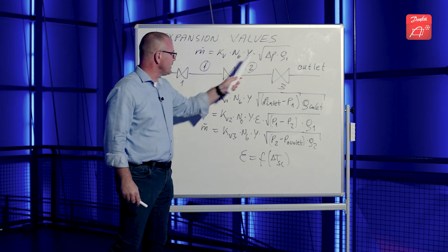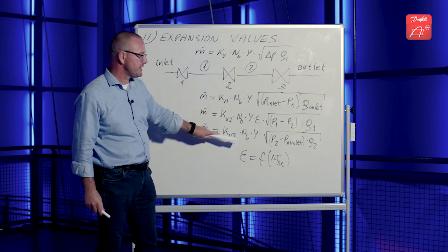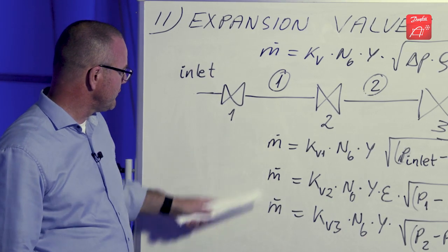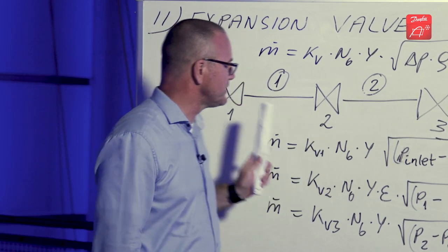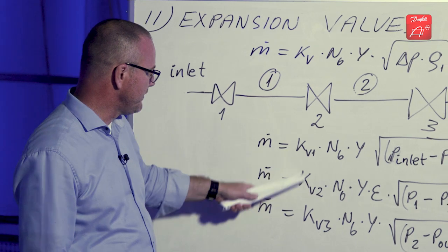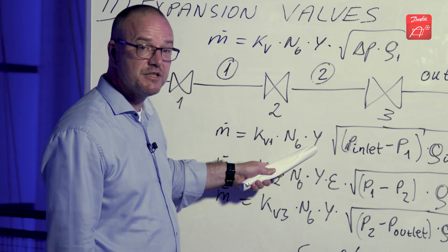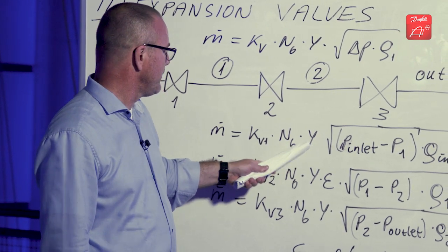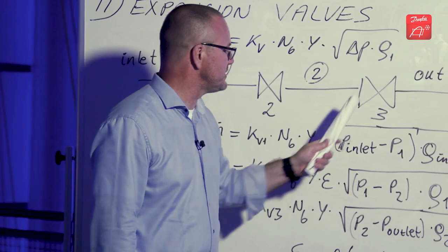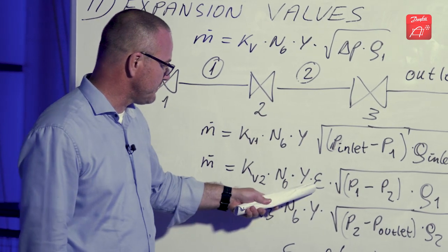But instead of having one equation, we now have three equations and we need to be able to solve this equation set. The mass flow we know because it's the same through all valves and it's normally given. The KV values we know. This constant we know. The net expansion factor. As we are approaching real situations, we normally just put that to one.